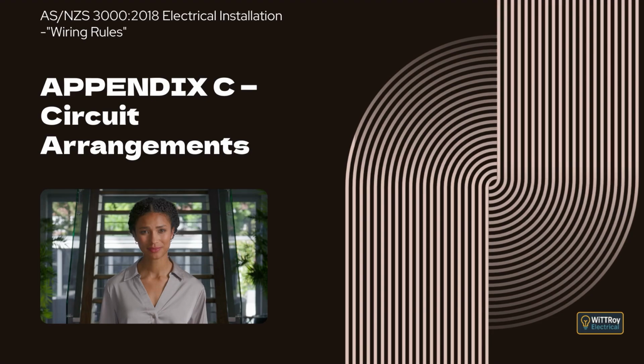Clause C2.5.1 General. This clause explains that diversity may be applied in some final subcircuits where equipment does not operate continuously at full load. Examples include welding machines, domestic cooking appliances, and interlocked equipment, where operating conditions naturally limit simultaneous loading.